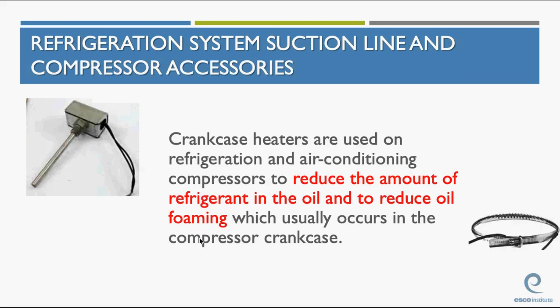Okay, crankcase heaters are used on refrigeration and air conditioning compressors to reduce the amount of refrigerant in the oil and to reduce oil foaming, which occurs in the crankcase on startup. Okay? We reduce the amount of refrigerant in the oil that's in the compressor. It's a crankcase heater. There's 2 types. There's one type that goes in a compressor well, that's up here on the top left, and there's another one that straps around the bottom of a compressor. These are energized either always or they're energized on the off cycle. In other words, when the system is not running. Be aware, there's energized components there. You can get shocked.